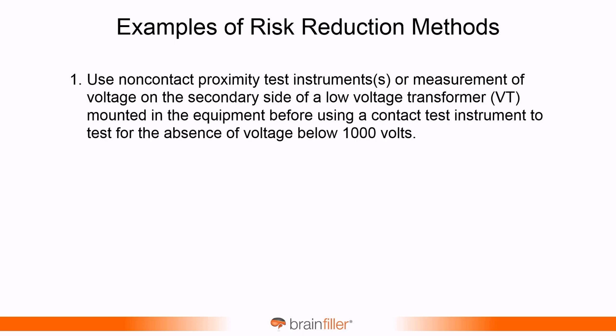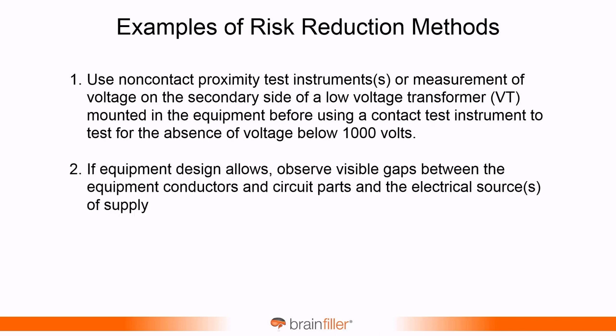Well, you can use a non-contact instrument to check and see if there's a voltage there, or measure on the secondary side of a voltage transformer. Some of us know it as PT, potential transformer, but voltage transformer, before you use a contact test instrument. So you're basically giving kind of a trial run here before you actually make contact. Another method, look for the visible gaps with the conductors. That'd be like a switch. You open, if you have access to actually look at a switch, is the switch open before you use a contact voltmeter.